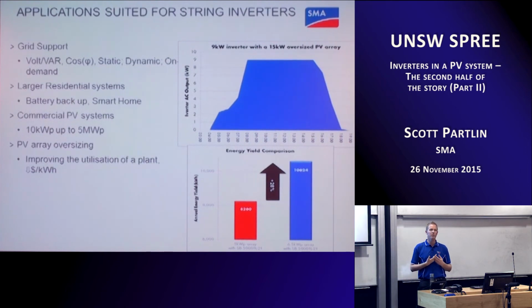So obviously within the PV industry, we've done a great job over the last 10 years in bringing the cost down, and the PV modules are now so cheap that the decision to add an extra couple is really just a decision of $500, $1,000. So keeping all of the other balance of systems fixed and only increasing the PV, you're able to increase, in this example, the energy generation by 28% while only increasing the cost of the system by 11, 12%. So that's something which is easier with a string inverter.